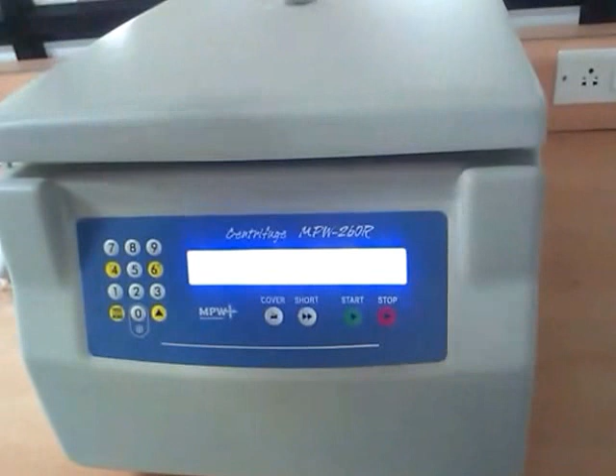Another part of the machine is that at the back end of the machine we have an RS-232 port, which helps it to connect with the computer or any external printer that might be available. All the parameters can be recorded, saved and printed through the PC from the machine. Another advantage of this machine, it has 10 acceleration and deceleration curves, which helps in smooth functioning of the rotor and smooth increasing or decreasing of the speeds. That's all about it.